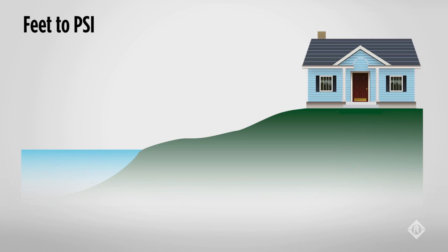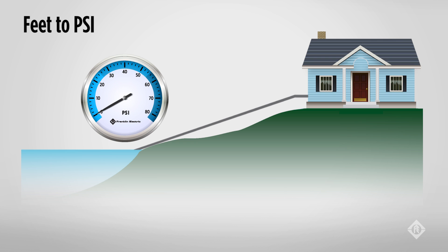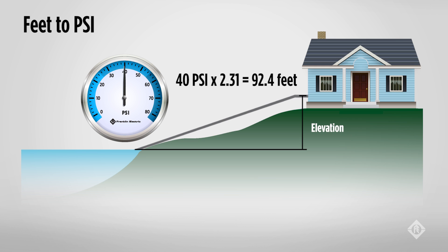Let's put this knowledge to practical use. Say we have a lake cottage on top of a bank and want to know how much pressure our pump will need to push water to the top of the hill. We don't have time or money for a surveyor, but we still need to know the elevation change from lake level to the cottage. If we take a garden hose or tube, run it up the hill, put a pressure gauge at the bottom, and fill the hose with water, we can determine the elevation. If the gauge reads 40 psi when the hose is filled, we know the elevation is 92.4 feet — simply 40 psi times 2.31 equals 92.4 feet. This is not distance but feet of head; we may have run 1,000 feet of hose to rise 92.4 feet, but either way we have 40 psi to overcome to pump water to the top of the hill.